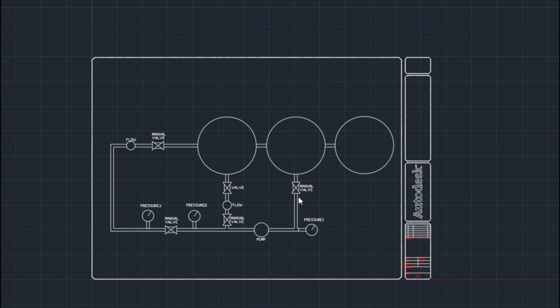So water is going to come out of this tank here, and we can read the pressure coming out of that tank. It will then go to the pump, and the pump will increase pressure and continue on to pressure 2. If this manual valve here is closed, we can continue flow this way, and we can dictate how much flow we get from this flow meter by using this valve. We're going to dictate pressure by using a PID with pressure 2 as our process variable. So if we're trying to maintain 50 psi and the system is at 30, the pump frequency is going to increase until we get to that 50 psi.